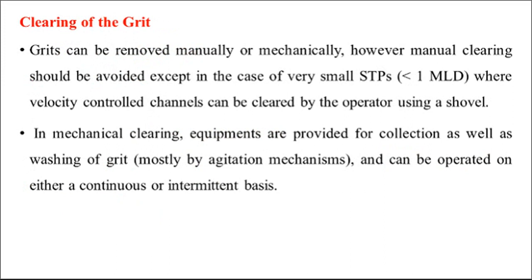Then clearing of the grit from the grit chamber. Grit can be removed manually or mechanically. However, manual cleaning should be avoided except in the case of very small sewage treatment plants having capacity less than 1 MLD, or 1 million liters per day, where velocity controlled channels can be cleaned by the operator using shovels.